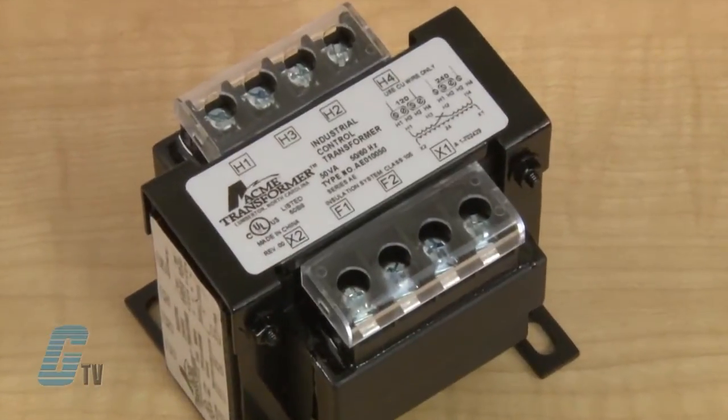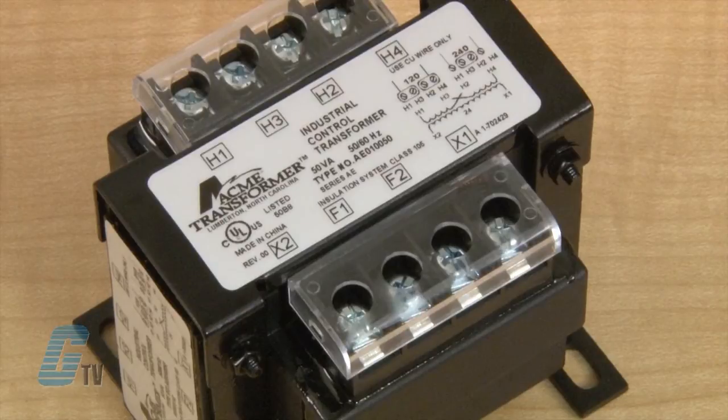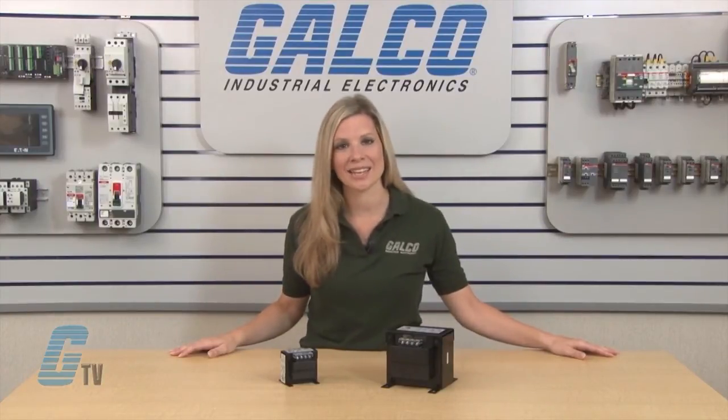The molded terminal blocks with isolation barriers prevent arc over and allow full access for solid termination with a full ring terminal. Fuse blocks are available as field or factory installed and can offer protection on the primary, or the primary and secondary.